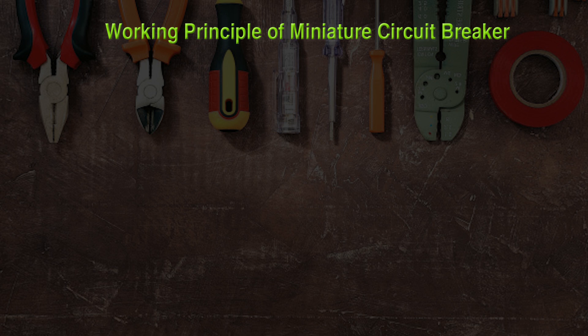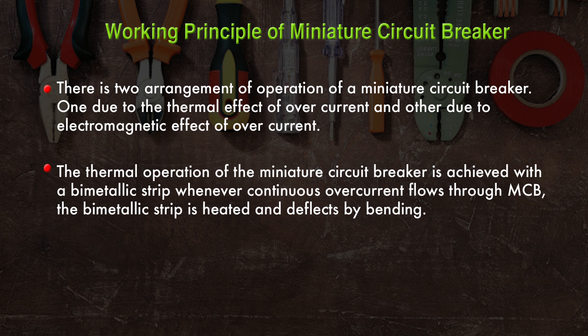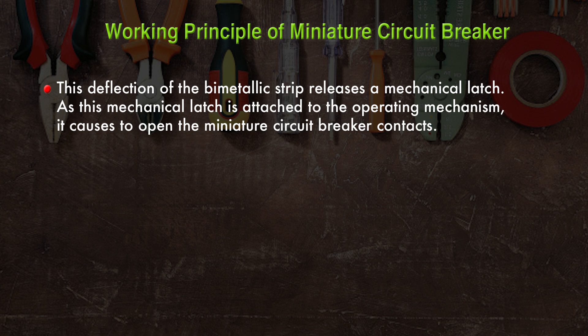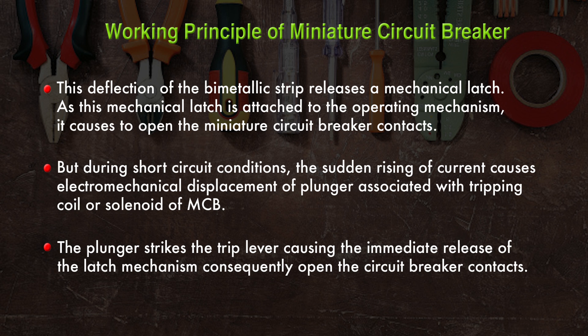The working principle of MCB involves two arrangements: thermal effect of overcurrent and electromagnetic effect of overcurrent. For thermal operation, a bimetallic strip is heated by continuous overcurrent and deflects by bending, releasing a mechanical latch attached to the operating mechanism, causing the MCB contacts to open. During short circuit conditions, the sudden rise of current causes electromechanical displacement of the plunger associated with the tripping coil or solenoid, which strikes the trip lever causing immediate release of the latch mechanism and opening of the circuit breaker contacts.